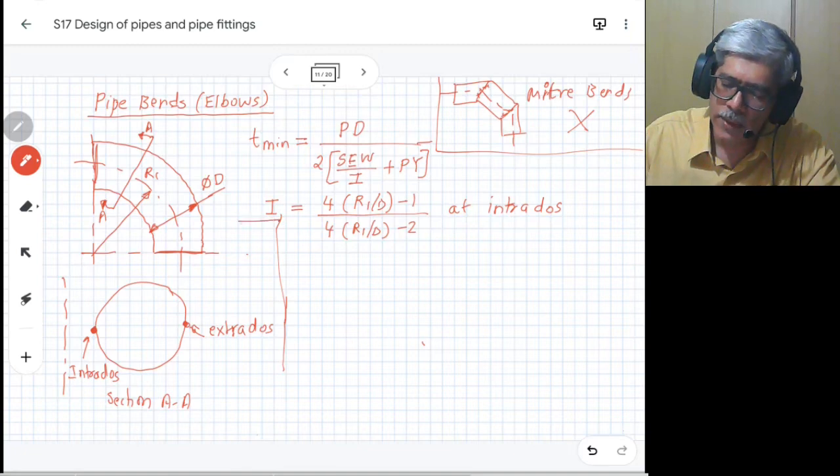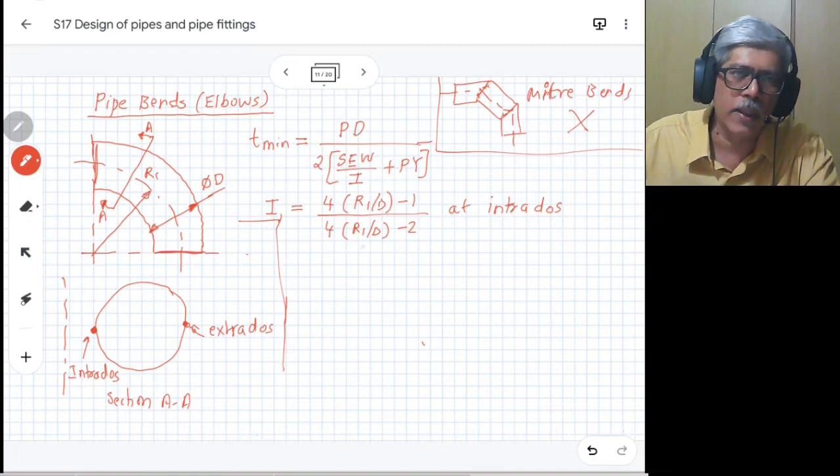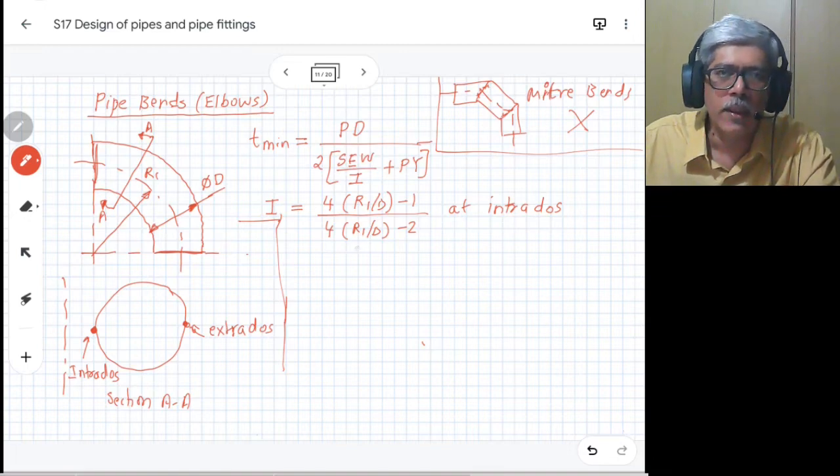The formula for the stresses - this I factor depends on which location you are calculating. Both at the inside as well as outside, the required thickness would be different.